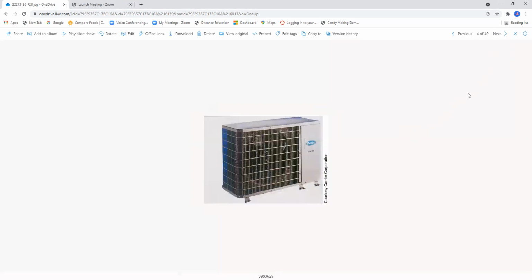This is an example of what they call a slimline condensing unit. You're going to utilize this type of technology. In fact, I'm doing a job in Rancho Cucamonga next week utilizing this very same footprint. The thing with this narrow profile condensing unit is that typically they're less than 24 inches in width, and I'm talking about front to back. These things typically are about 4 feet high. And then, of course, the condenser fan is mounted in a horizontal position.